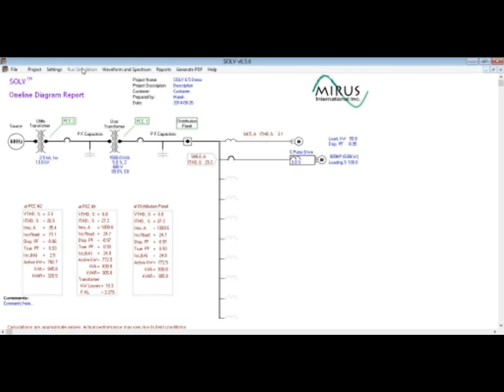And depending on the model complexity, this may take a few seconds. This time it was quick, but sometimes when the system is defined with many different nonlinear loads, it takes a little bit longer. After the calculation has finished, simulation results are on the one-line diagram at each load branch. Also shown in the table here for distribution panel, user transformer secondary, which is defined as PCC1, and utility transformer secondary, which is defined as PCC number 2.